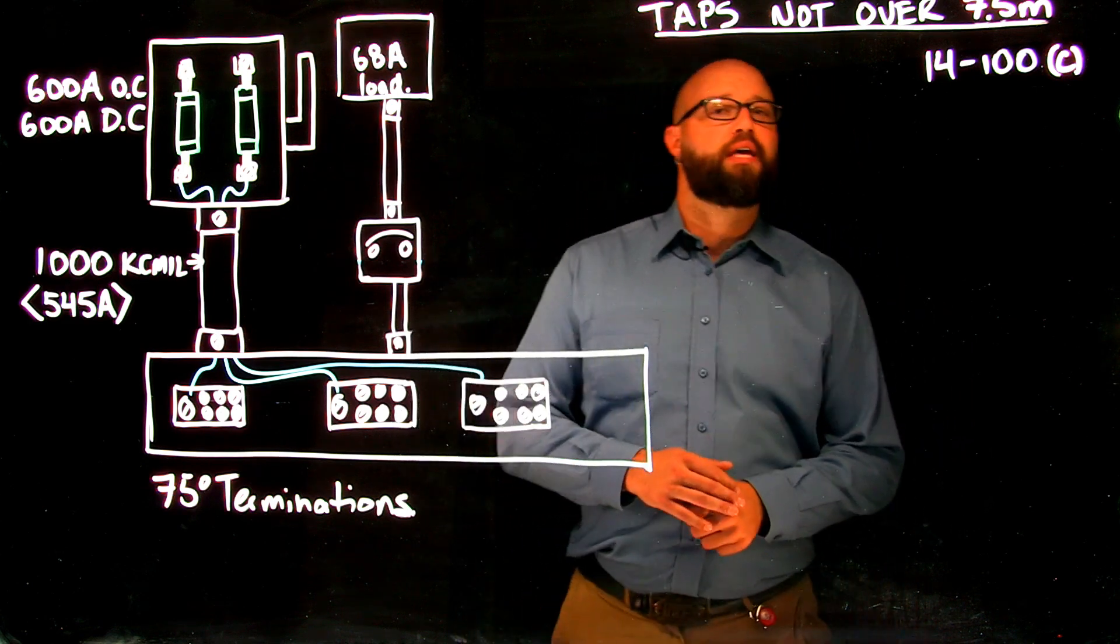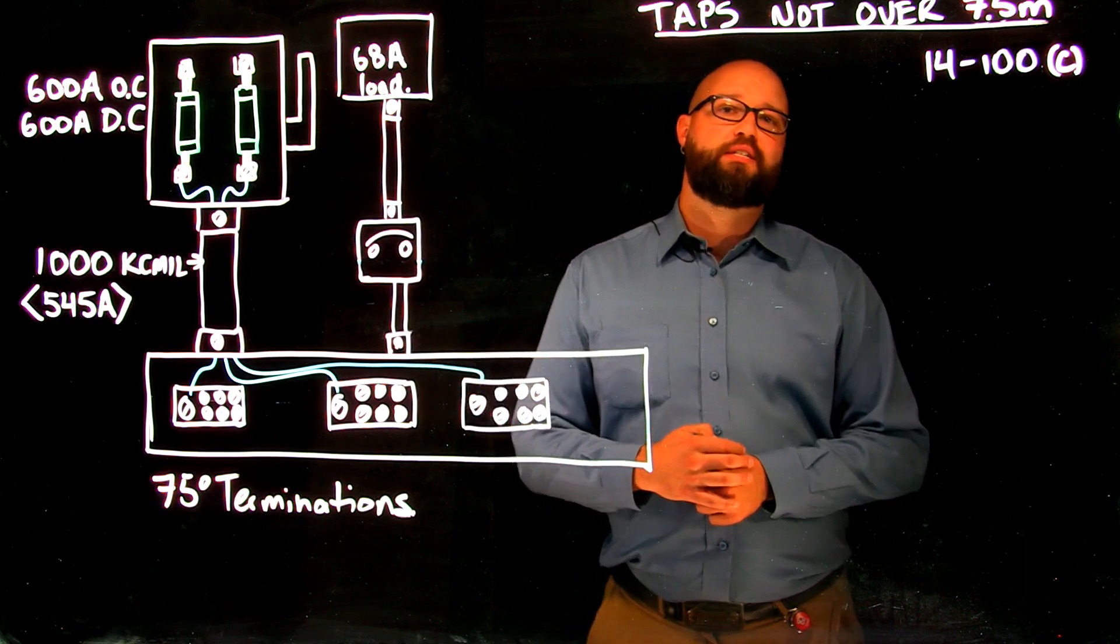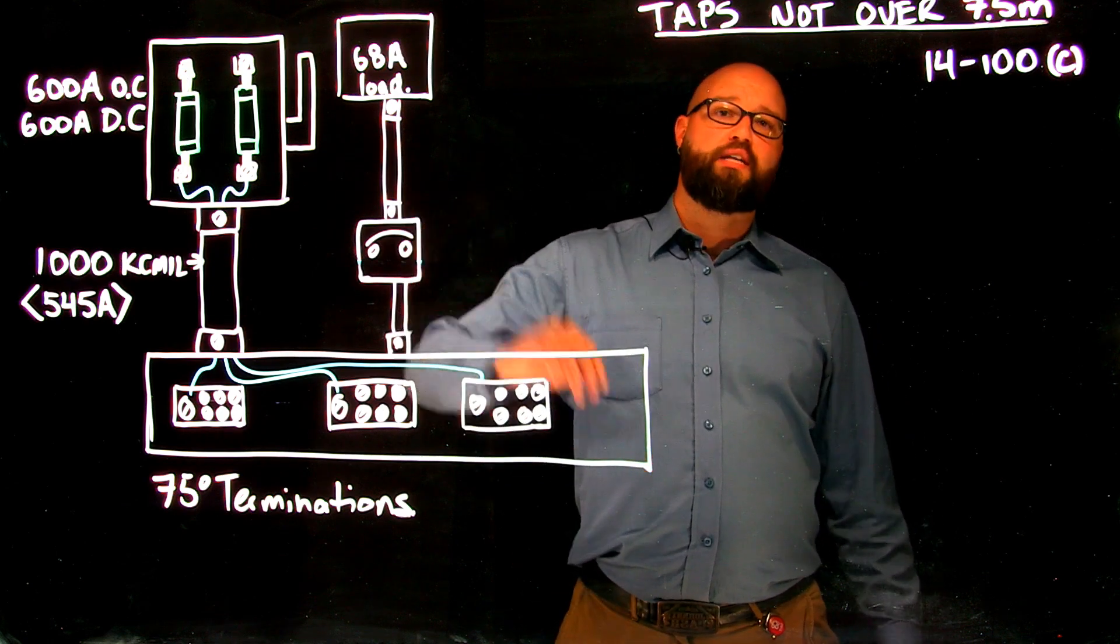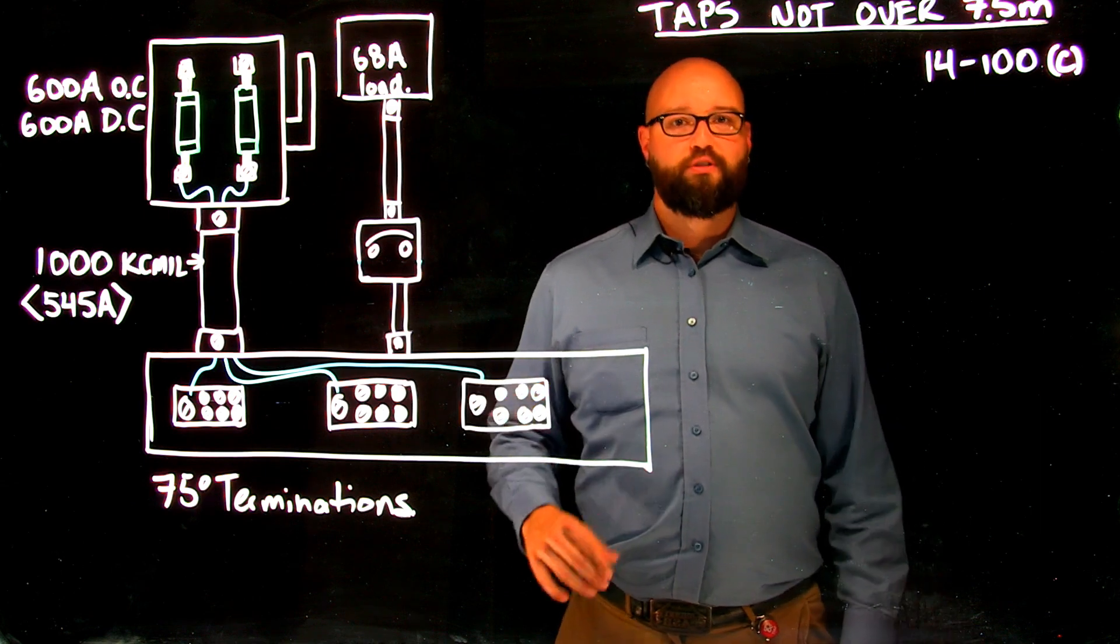First thing I want to point out before we get into this is that by the rule 14100 we are not allowed to downsize our conductor without overcurrent protection unless it is on the downstream side of an overcurrent device. There are exceptions to the rule.